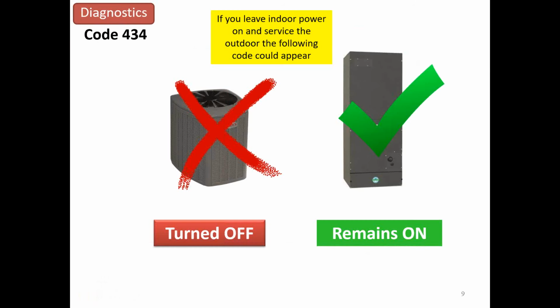A pretty common occurrence that I get quite regularly is if you leave the power on the indoor unit on and the outdoor unit off, then it loses communication to the outdoor unit and it's going to throw a code on it. It will automatically reset, but you can just cut the indoor section off and power it back up with the outdoor unit on first, and then it will go away.